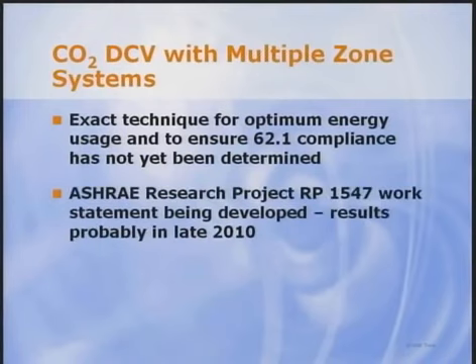Or we could increase the outdoor air minimum position, but this will increase outdoor air to all zones, not just this zone. If the outdoor air temperature is below the supply air temperature set point, this can increase heating energy. And if the outdoor air temperature is above the supply air temperature set point, this will increase cooling energy. So, which is the most energy efficient? We don't know yet exactly. That is part of the ASHRAE research project.